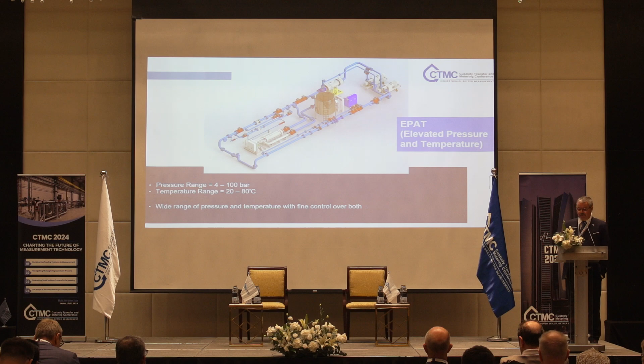Here I have a mass flow meter. It's a Coriolis meter. If there are Coriolis meter manufacturers here, they know all this. I'm not here to decry their product. Fantastic meter. So I've calibrated that meter at 5 bar, and it looks spot on. 0.1% maximum deviation from the reference. Everybody's happy. Low pressure calibration in line with the manufacturer's specification and industry expectations.